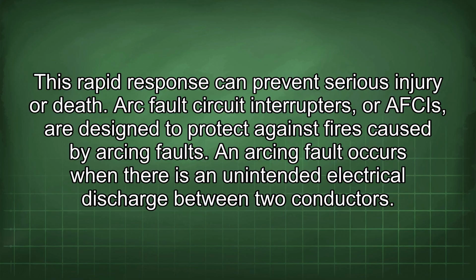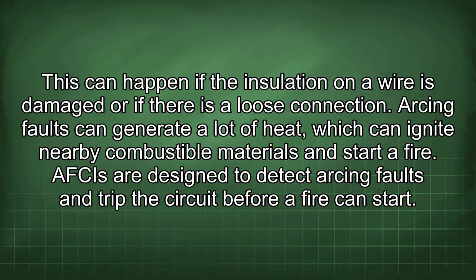Arc fault circuit interrupters, or AFCIs, are designed to protect against fires caused by arcing faults. An arcing fault occurs when there is an unintended electrical discharge between two conductors. This can happen if the insulation on a wire is damaged or if there is a loose connection. Arcing faults can generate a lot of heat, which can ignite nearby combustible materials and start a fire. AFCIs are designed to detect arcing faults and trip the circuit before a fire can start.